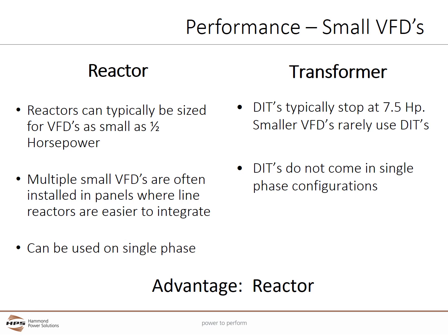As we discussed previously, small VFDs often don't have DC link chokes. As a result, the smaller VFDs will produce more harmonic currents per motor amp than larger VFDs with DC link chokes. Applications with many small VFDs, like distribution centers with conveyors, can have significant harmonic current issues. Smaller VFDs are also more likely to be fed by transformers, which can supply 10, 20, or more times the load of the individual VFD.